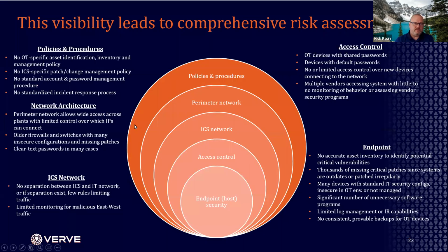And the other thing about getting this level of data is, as I've alluded to before, the assessment portion. We don't need to do an annual assessment anymore when I can look at this every day in real time. I can get endpoint data, which is very clear. Is it on there or not? Is the patch present or not? Is the control hardened or not? But we can also see shared passwords, group policy inheritance, like I said about the password. We can also see network violations of communications between different areas. We can see dual-homed systems. Like I mentioned, that one client, we found 5 dual-homed systems, 4 of them running TeamViewer.